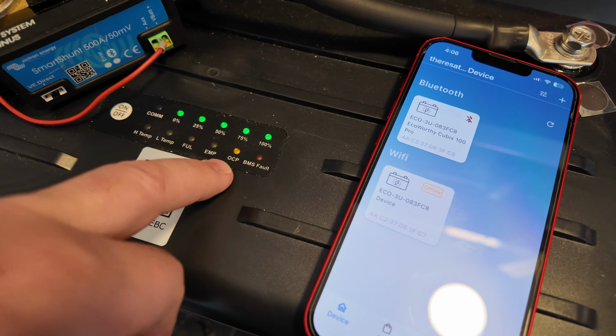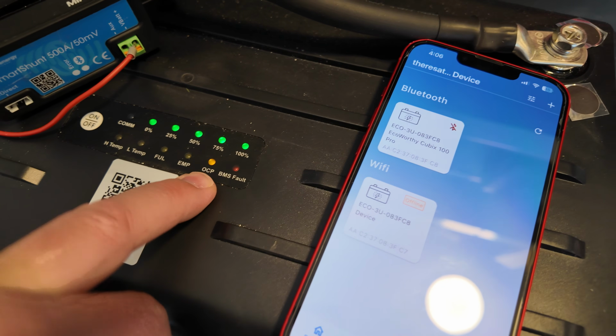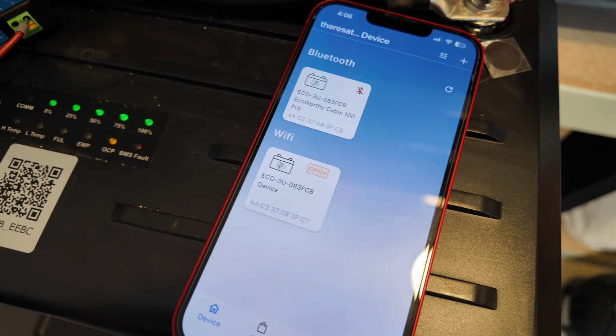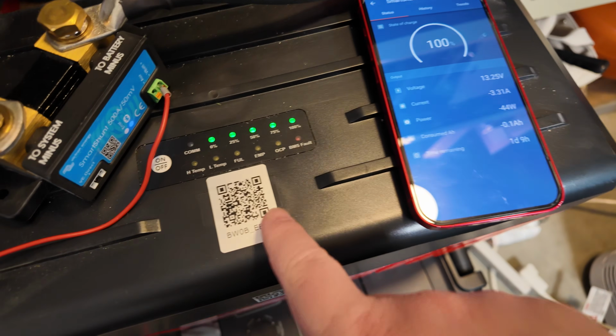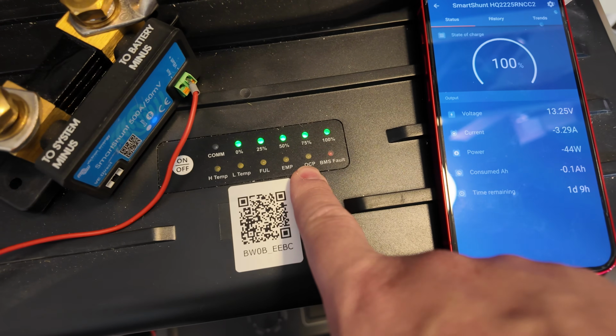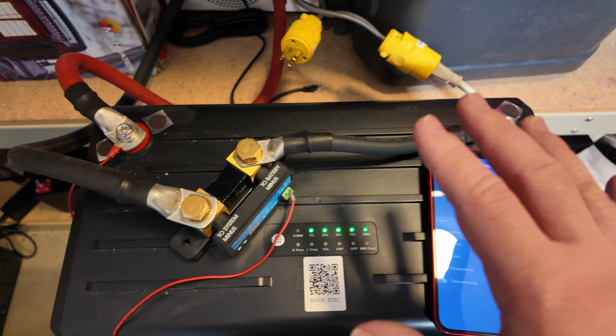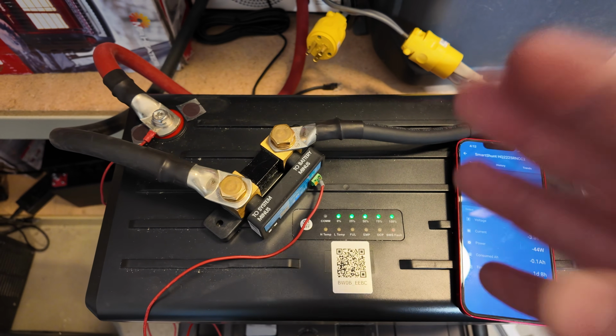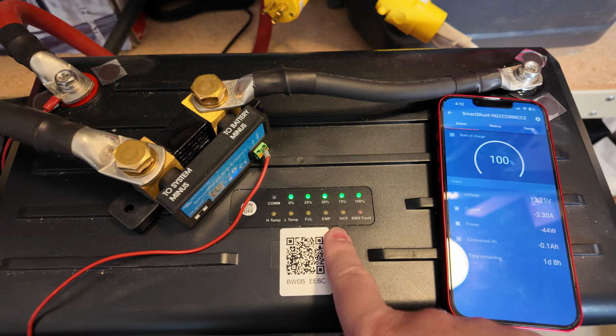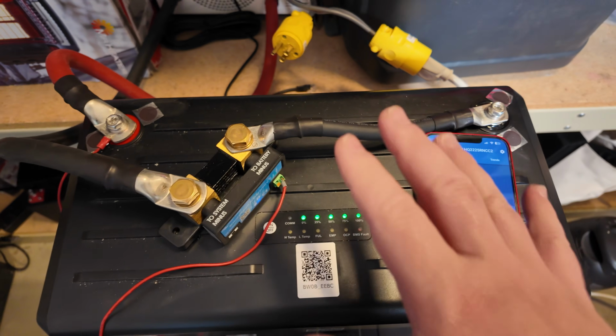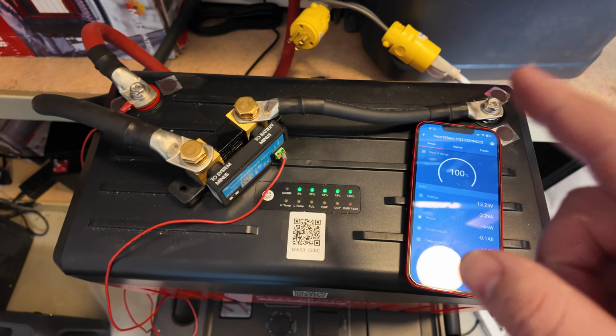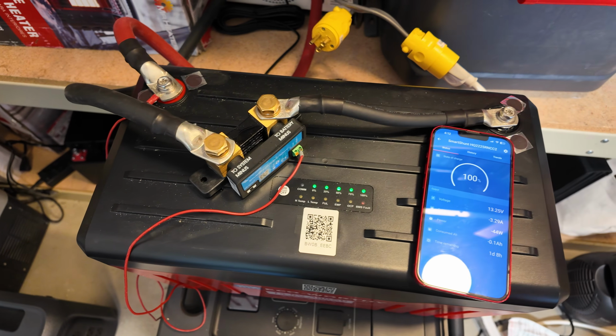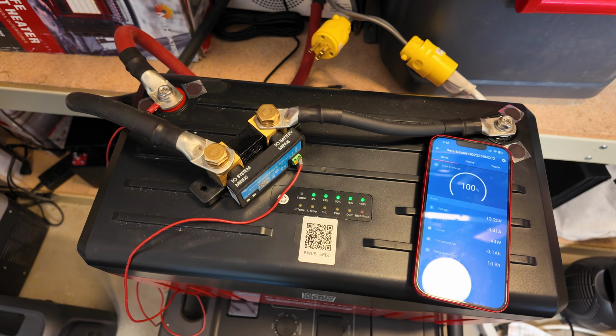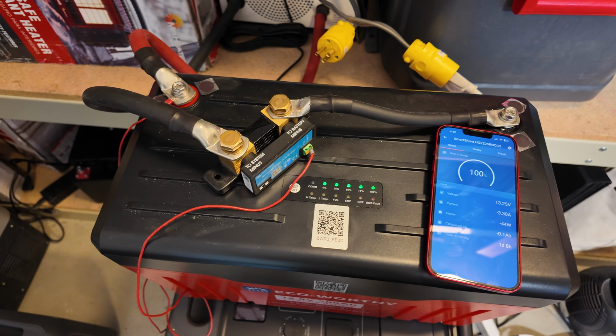A little while later, and you can see we're still in overcurrent protection, the app is still not connecting. Okay, I've got to restart it. You can see we cleared the overcurrent protection error here, but I did have to put a charger on the posts, a 0-volt charger, one that can wake a dead battery up, because this was not restarting on its own, which isn't necessarily a bad thing. Just be aware that you will have to kind of wake it up with a 0-volt battery charger of some kind if it goes into overcurrent protection.